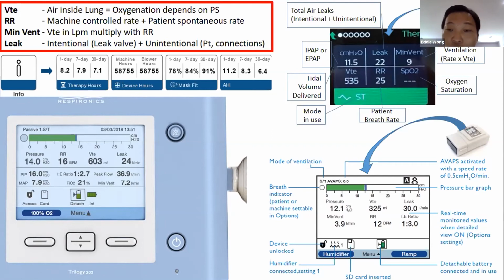Let's say a doctor told you this patient must have at least 400 ml. So you check if this is not because of the rate dropping too low. Then the next thing you check is if this is not because of the volume dropping lower than 400. Let's say the volume is 400, but the rate becomes 0, meaning the patient is not triggering, or a circuit disconnection. It can also cause this low minute ventilation.